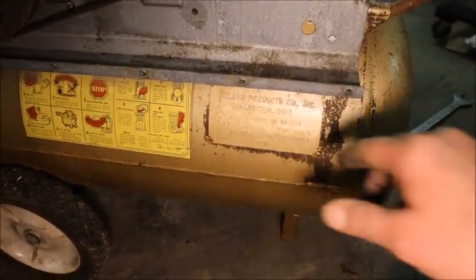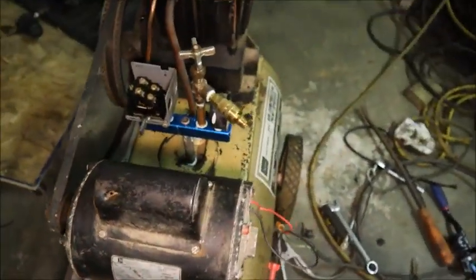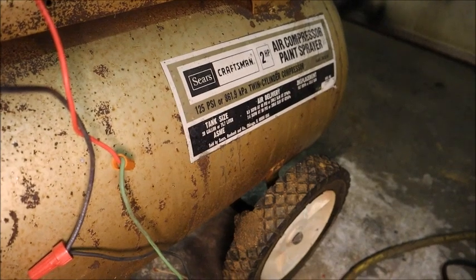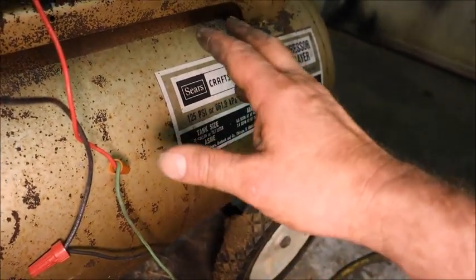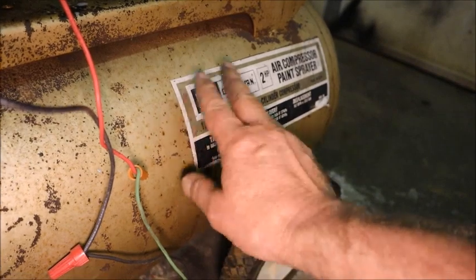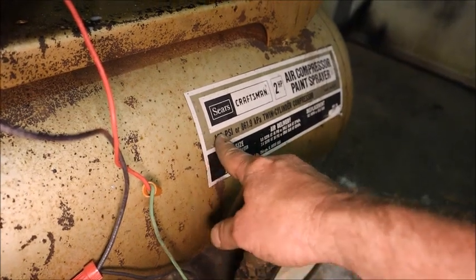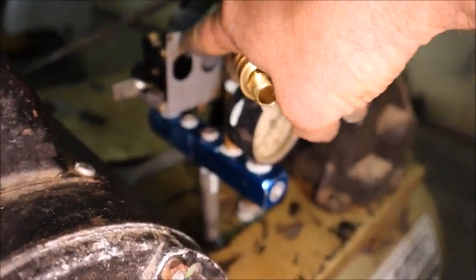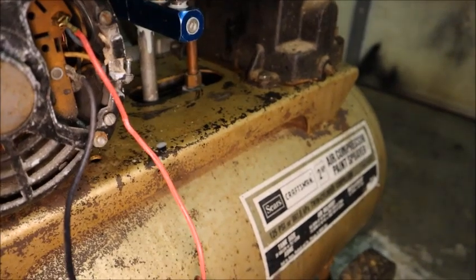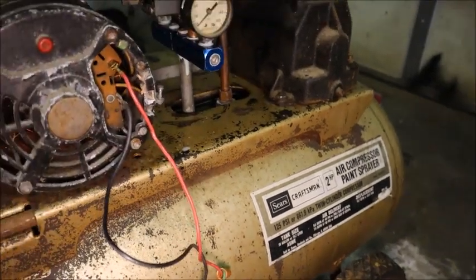We proved that at 150% of rated pressure the tank is not going to rupture. The machine as a whole is rated at 125 psi, so there's even more margin — if it took 244 pounds, 125 is perfectly safe. I'm going to get a relief valve set just above 125 psi for the middle port, and I'll also need to replace the broken pressure switch and set it to 125 psi. This will be safe to use. Hope you all enjoyed seeing me test this tank and start to put it back together — thanks for watching.